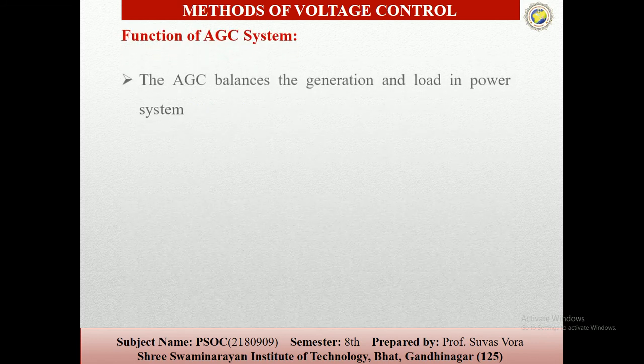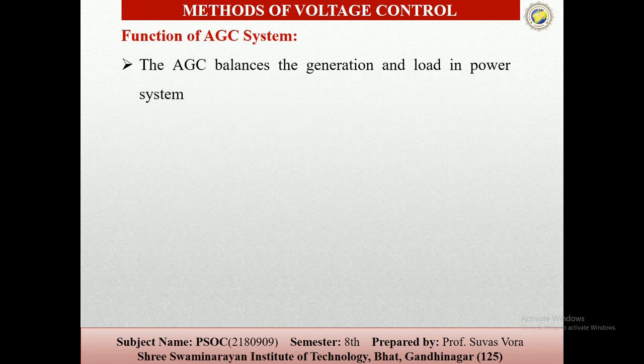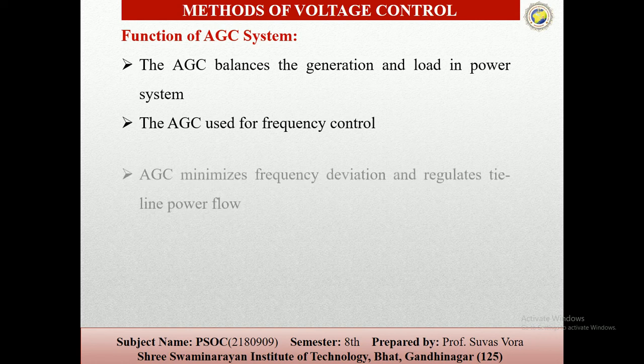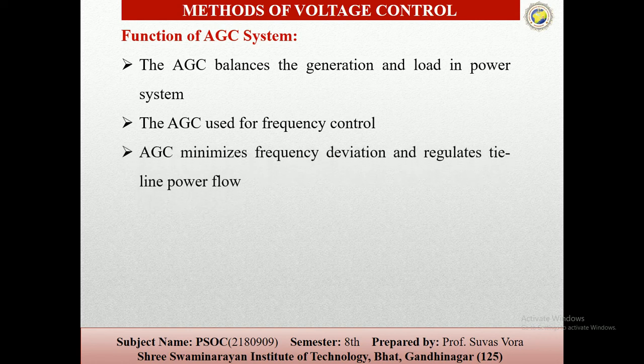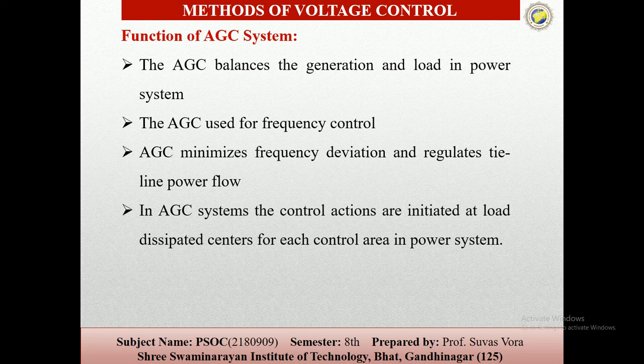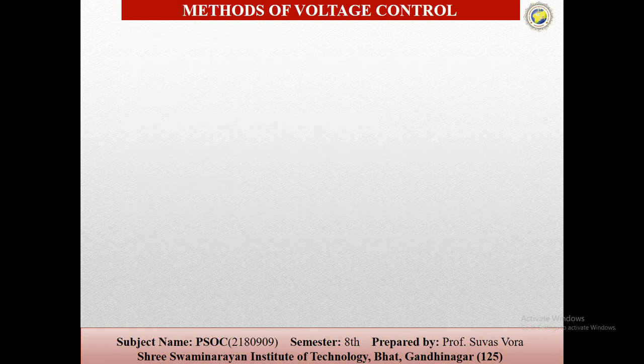So the function of the AGC system is to balance the generation and the load in the power system. Then it is used for frequency control, to minimize the frequency deviations, and it regulates the tie line power flow. In this system, the control actions are initiated at the load dispatch center from each control area in the power system.